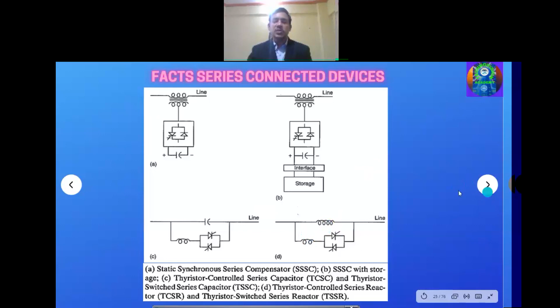You can connect a capacitor in series, and you can apply circuit breakers for opening, or taking that system out, and managing the rest of the system. We know that a capacitor stores high reactive power, so the charging current is high. Because of that, if I open the breaker, there is a release of high stored energy, and to damp out or absorb that energy into the reactors, we want such an arrangement. The circuit breakers are also used to disconnect, to work on these systems during the maintenance period.